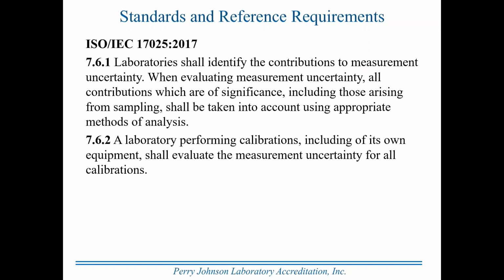Every calibration they do, even if they calibrate the same device year by year by year, the uncertainty is expected to be slightly different from time to time because of the random variations, typically not systematic variations, but random variation contributes to that. Non-repeatability, you don't get exactly the same answer on a measurement from year to year. So every year that you would calibrate that machine, you have to estimate its uncertainty under the conditions that exist at that particular time.